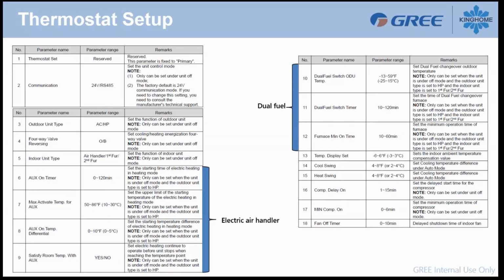Number 9 is satisfy room temp with auxiliary heat. So this is only a reverse stage, if I can say so. If yes is selected, you will keep the electric heat active until you reach the set point temperature. If it says no, then your duct heater will turn off when the temperature is close to the set point. So basically, that will also add more energy savings to the system, because we want to turn off the duct heater most of the time, but if needed, it's there to help the system perform. So this is about the thermostat.